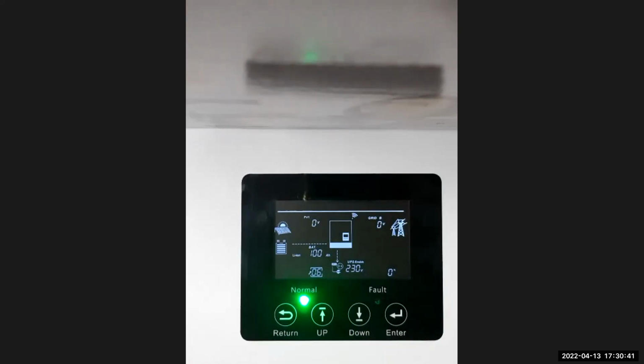Number 6 is your charging current. So number 6 is the maximum allowed amount of charging current this unit will give to the batteries. This is the value, even if the BMS of the battery is asking you for 60 or 70 amps, but you limit it to, let's say, 50 amps. Your inverter won't charge higher than 50 amps, even if the BMS is requesting higher than 50 amps.